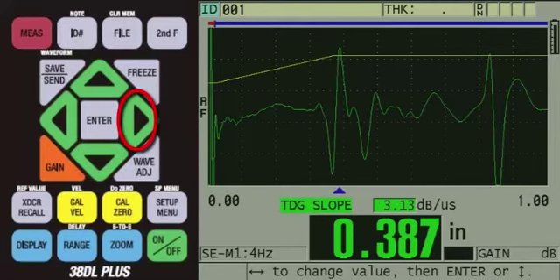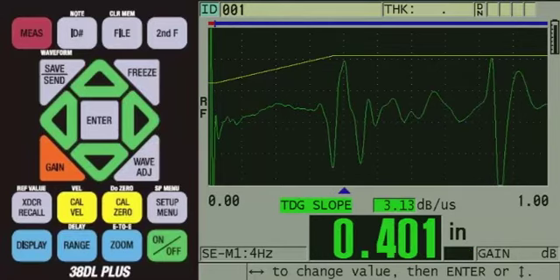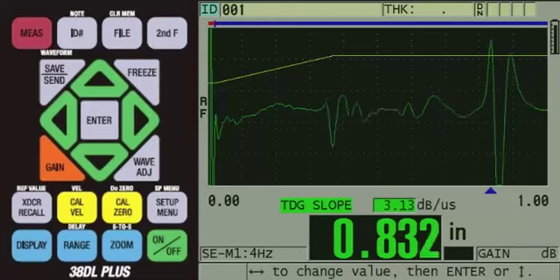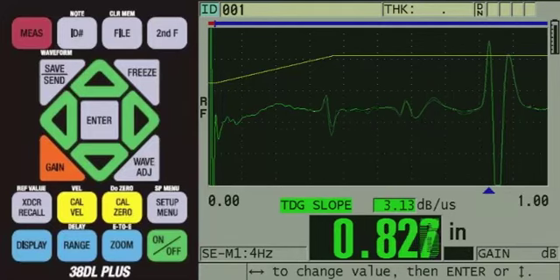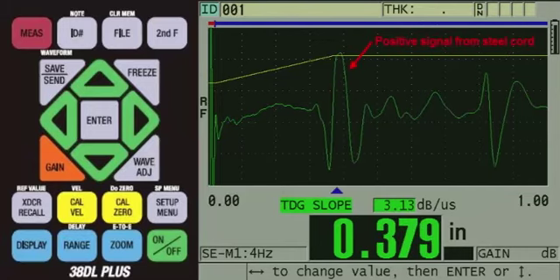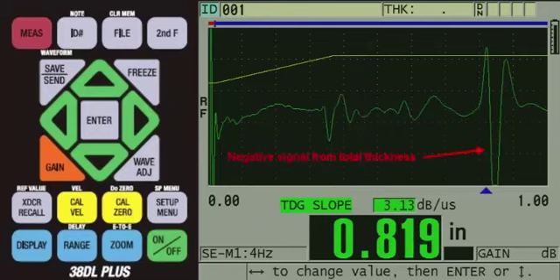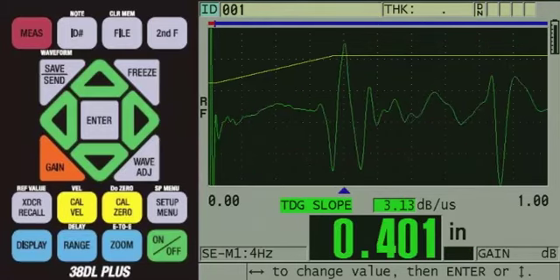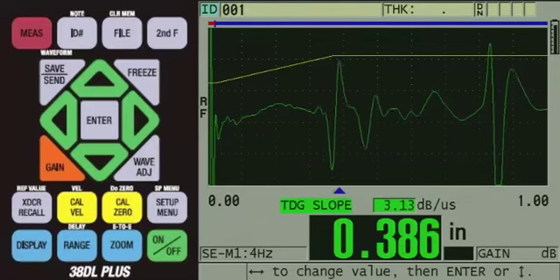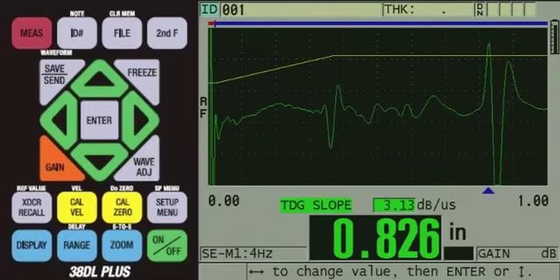signal is being detected. At this point, we should be able to scan the transducer across the conveyor belt sample and see where there are steel cords and where there are no steel cords. It is important to remember that the polarity of the signal changes when measuring to the steel cord versus when measuring total thickness. Therefore, the user will either need to change the echo 1 detection depending on the measurement, or if they would prefer, they could save 2 separate custom setups.